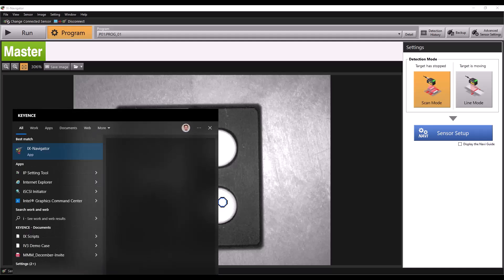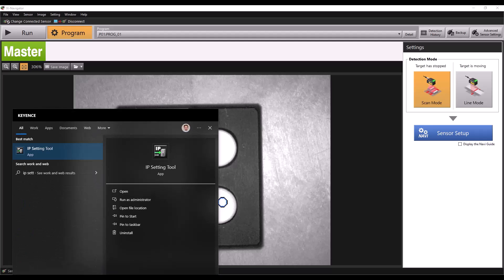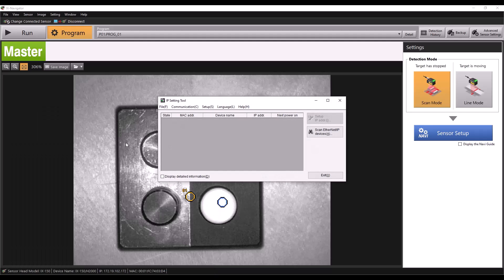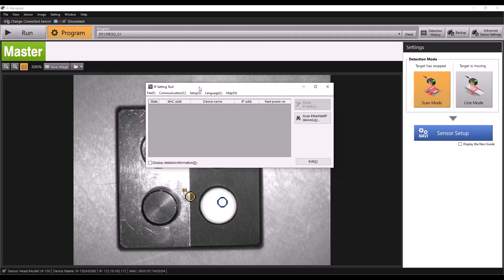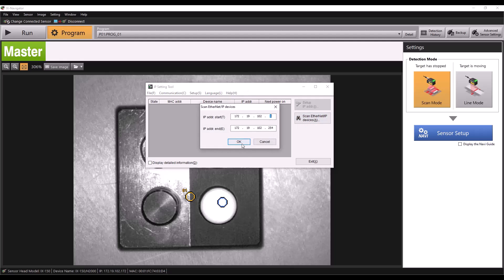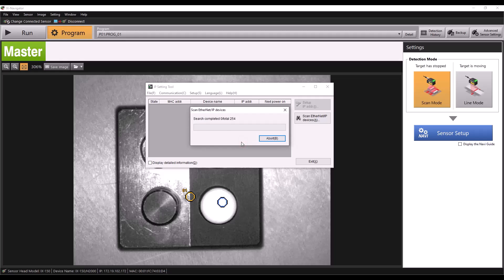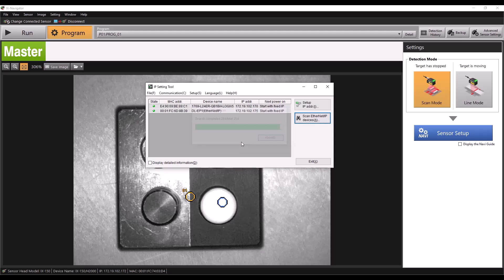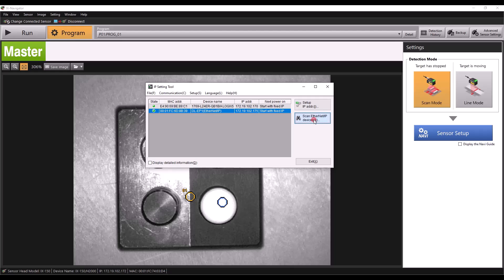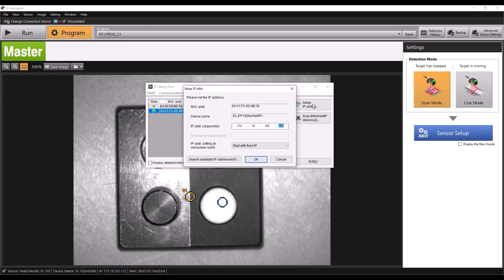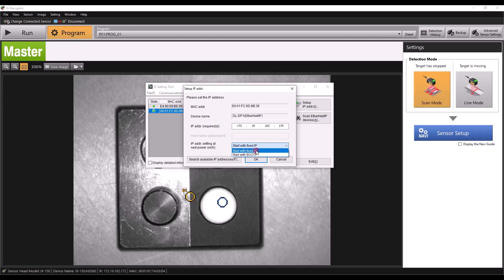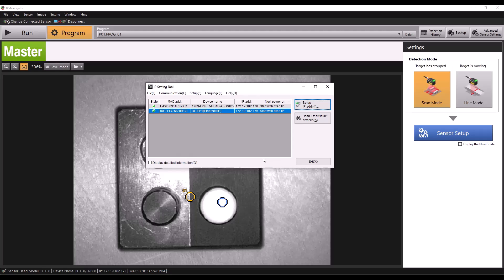The last step before establishing communication with our PLC is to set the IP address of our DL EP1. We'll do this using the Keyence IP setting tool, but any IP setting software can generally be used. I'll click scan Ethernet IP devices then OK, and it will search the network for Ethernet devices. We see our DL EP1 is on the network, so we'll click that then click set up IP address. My device already has an IP address, but if you're setting up your DL unit for the first time it will not. Simply assign it an IP address and select start with fixed IP address then click OK. Now that we've set the device's IP we can head to Logix Designer to establish communication.